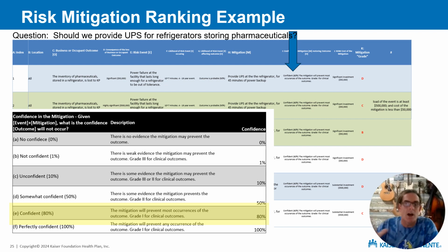Now we have to look at the confidence of the mitigation. If we put a UPS in here, then how confident are we that that's going to save those drugs? And in this case, it's not. We can't consider it perfectly confident because UPS doesn't buy us an infinite amount of time to save the drugs. It buys us about 45 minutes. So the power outage happens, the UPS continues to provide power, you got 45 minutes to get those drugs out of there. That's good. That's something we can have some confidence in, but it is definitely short of perfect confidence. So we call this confident, right?